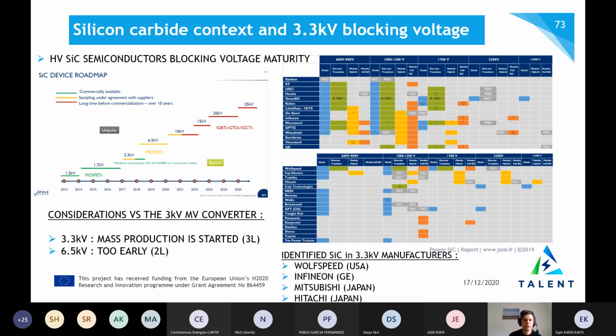And for semiconductors with blocking voltage superior to 3.3 kV, we see that it is not mature yet. You have samples that are really expensive, but for industrialization, it's not really suitable to use this kind of blocking voltage, even if it's really interesting from a technological point of view. 3.3 kV is not yet in mass production, but it is shifting more and more into mass production. So we have selected this blocking voltage for the silicon carbide module.